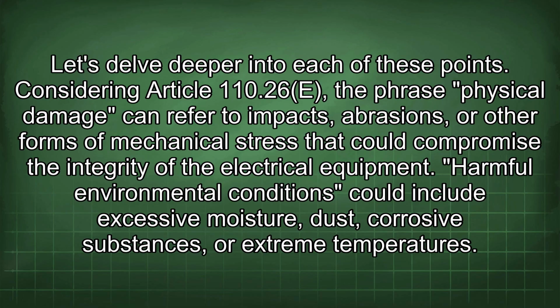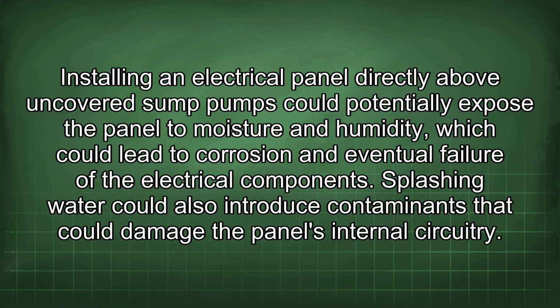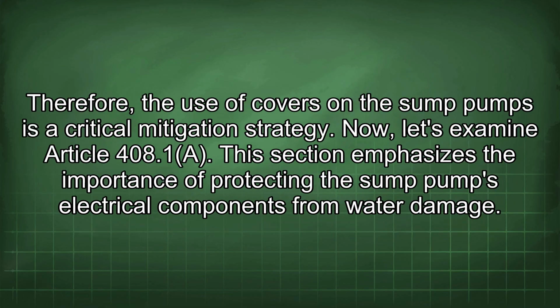Considering Article 110.26e, the phrase physical damage can refer to impacts, abrasions, or other forms of mechanical stress that could compromise the integrity of the electrical equipment. Harmful environmental conditions could include excessive moisture, dust, corrosive substances, or extreme temperatures. Installing an electrical panel directly above uncovered sump pumps could potentially expose the panel to moisture and humidity, which could lead to corrosion and eventual failure of the electrical components. Splashing water could also introduce contaminants that could damage the panel's internal circuitry. Therefore, the use of covers on the sump pumps is a critical mitigation strategy.